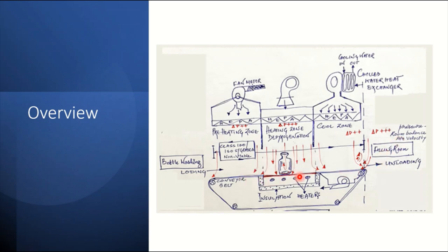We can see red arrows showing pressure differentials. The preheating zone air is going towards the washing room, so this high-pressure area is not allowing the washing area to enter the preheating area. The filling room is entering into the cool zone partially, ensuring that your filling zone is not getting air from the tunnel. The heating zone is a pressurized zone where the pressure is towards the cool zone and preheating zone.